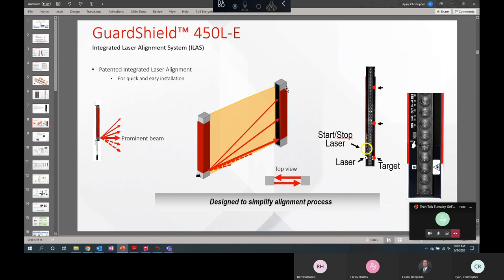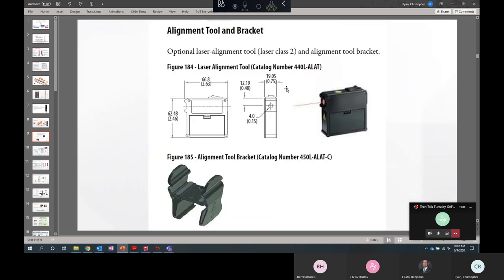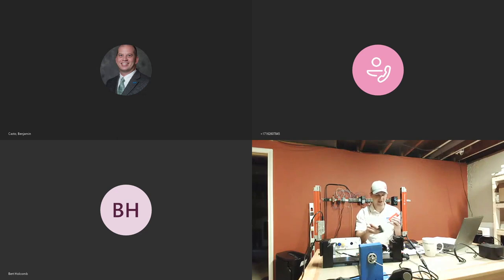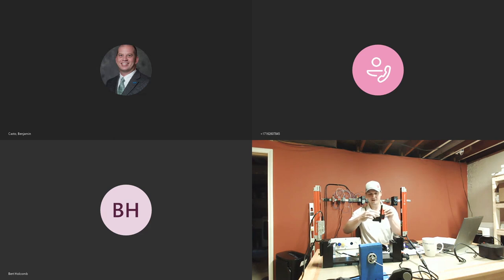So for the 450LB with the basic model, it doesn't have the integrated laser alignment system, but you can use a snap-on tool, an accessory to help with that. And I will show you that. So you just take your 450LB here, and if you don't have integrated laser alignment, you just take your laser, your 440A-LAP, and you snap it onto your bracket like that, snap it to your light curtain, and you can use this very similar to the integrated laser alignment system on the enhanced model.